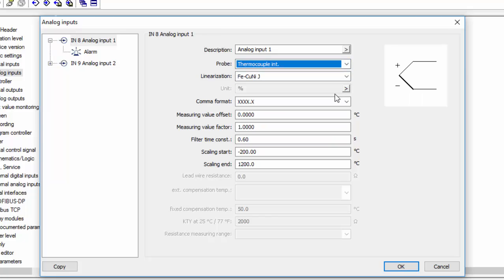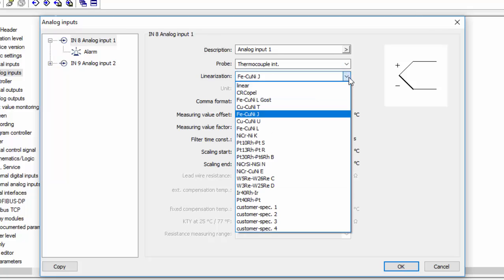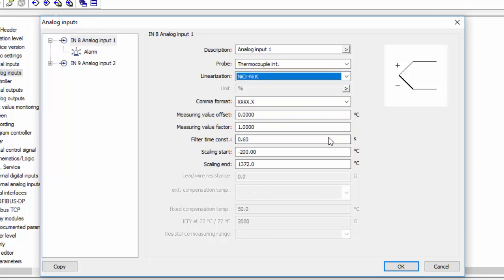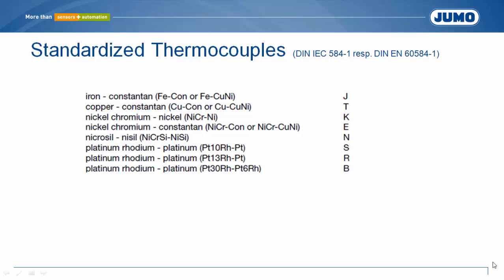The selection of the thermocouple used is carried out under linearization. By means of this selection, the associated temperature is automatically formed from the measured thermoelectric voltage. A selection of thermocouples is defined. The voltage characteristic and tolerance of the respective elements are standardized. Here the symbolism of the thermocouple is shown. The minus leg is drawn thicker.